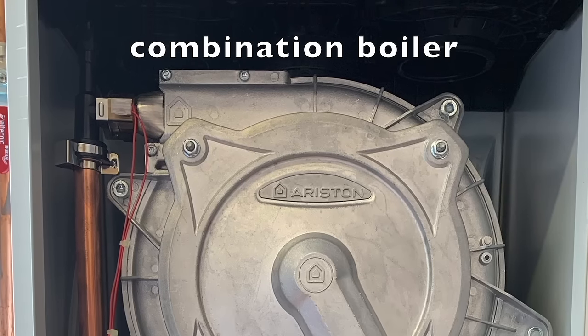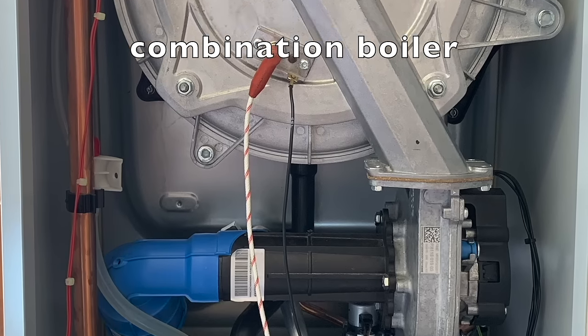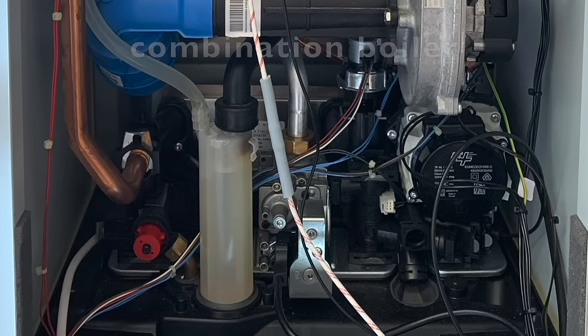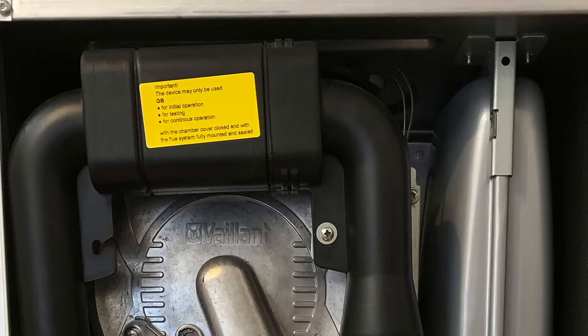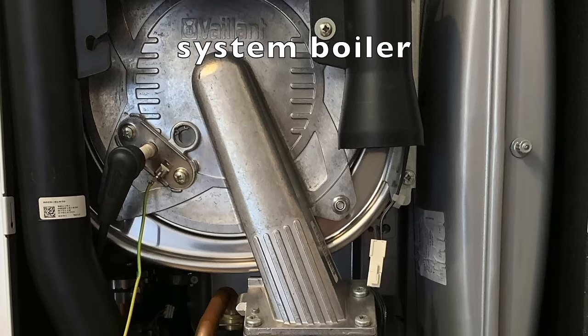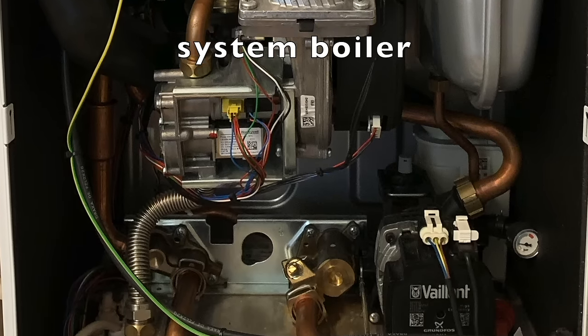The combi boiler, or to give it its full name, the combination boiler, is the name given to a boiler that heats central heating and heats the water instantaneously at the hot tap. The other types, as we've been looking at them, the system boiler, which is basically a combi boiler without any way of heating the hot water. It does have things like a pump and expansion vessel like a combi boiler does, but you need a hot water cylinder or an unvented cylinder to heat your hot water.